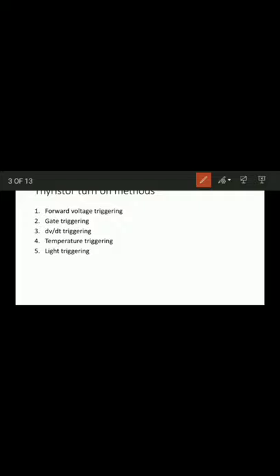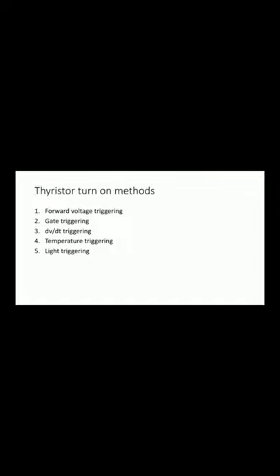Light triggering: here, laser light is used. The device used is called an LASCR (Light Activated SCR). The LASCR may be triggered with a light source or with a gate signal. Light-triggered thyristors are useful in HVDC (high-voltage DC) transmission systems. These are the five turn-on triggering methods of the thyristor.